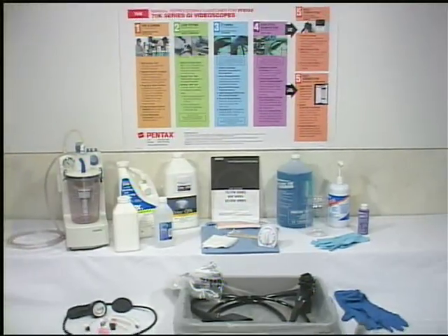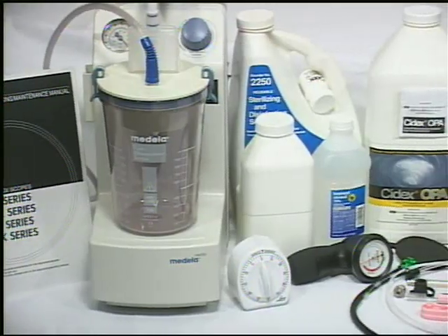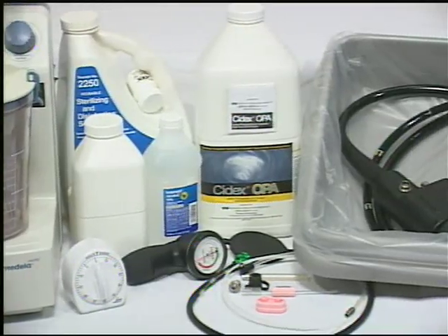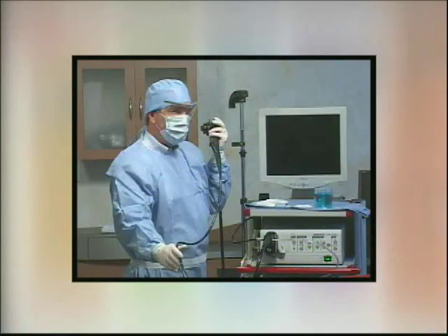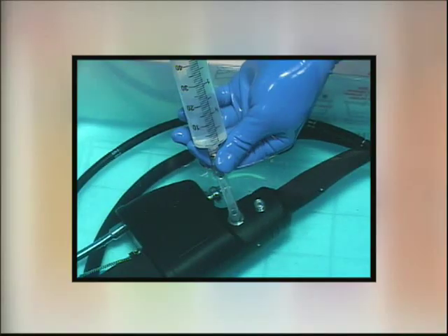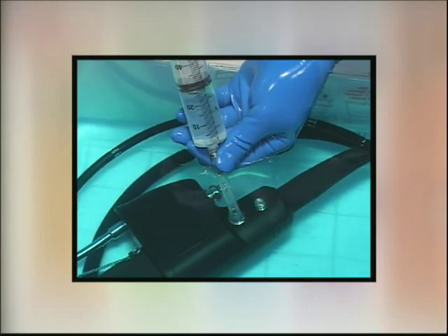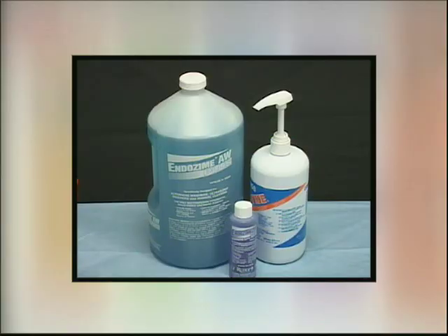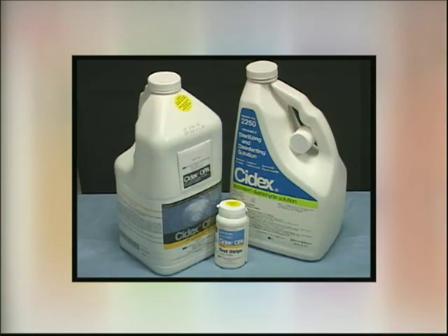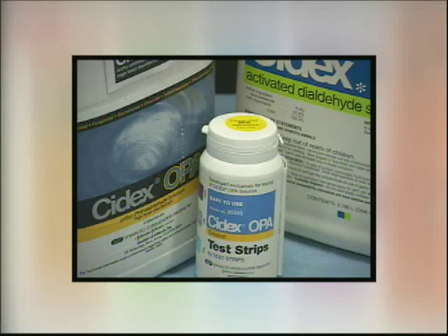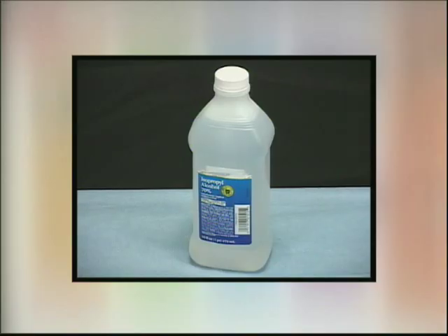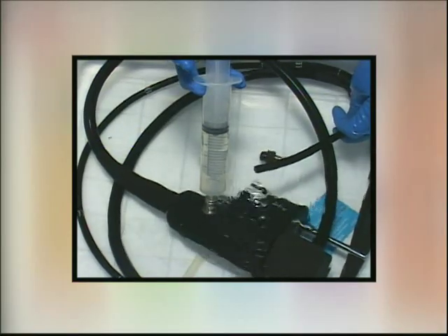Preparation: needed supplies. The following is a list of some of the most important supplies required to reprocess your Pentax flexible GI endoscopes. Personal protective equipment such as face shield, eye protection, full-length gown with elasticized wrists, and gloves. Gloves must be suitable for the particular reprocessing agents used. Compatible enzymatic detergent. Compatible high-level disinfectant. Chemical indicator or MEC test strips to check the minimum effective concentration of the active ingredient in the liquid chemical germicide. Isopropyl alcohol. Sterile or microbe-free rinse water.